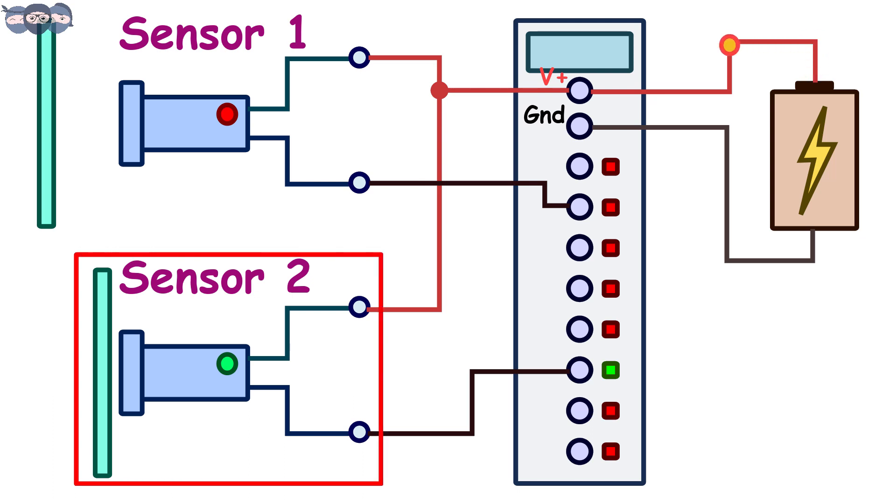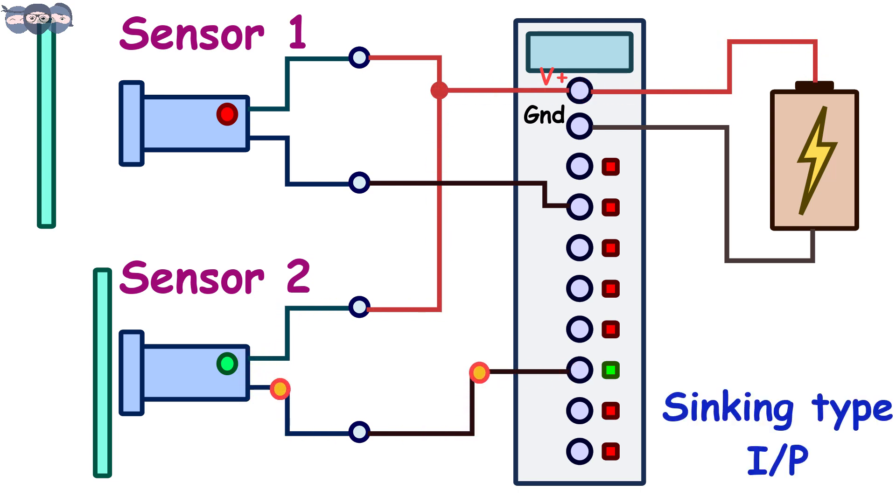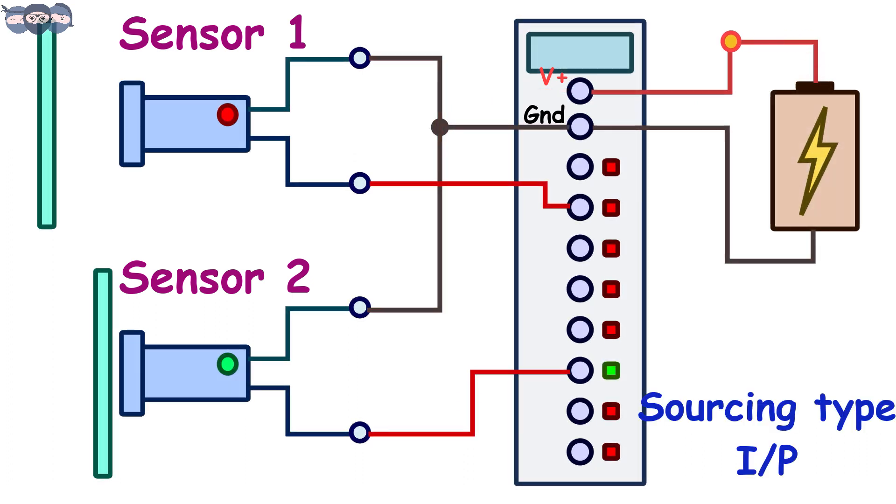When a sensor is triggered, current first flows into the sensor as shown in the animation and then into the input module. Hence, the input module acts as a sinking type. The same analogy can be used for a sourcing type input module.